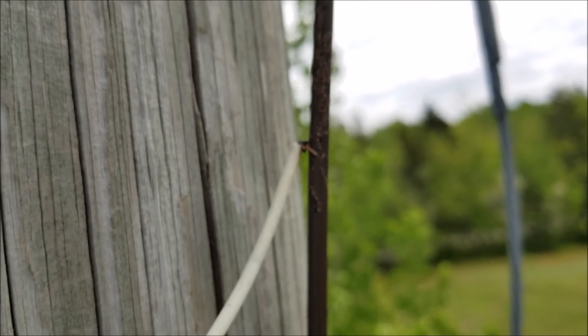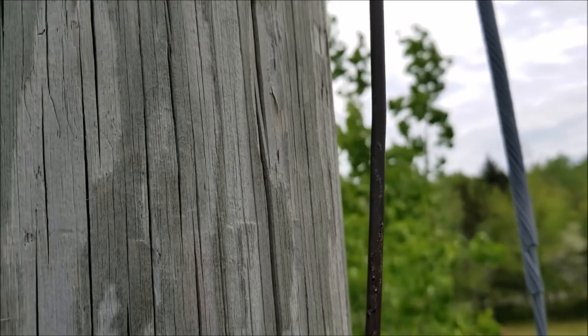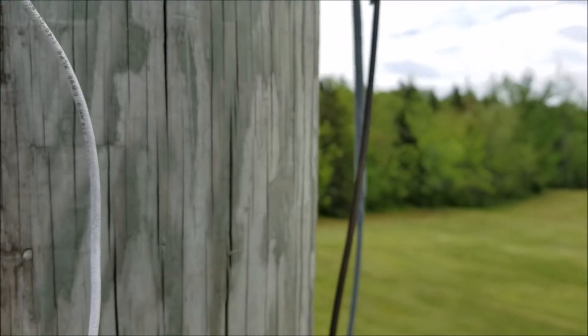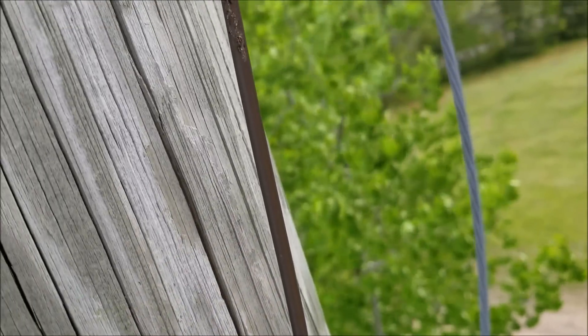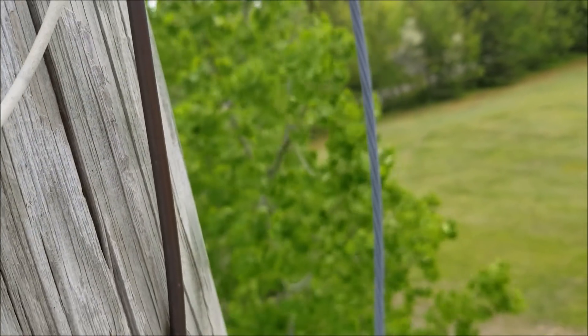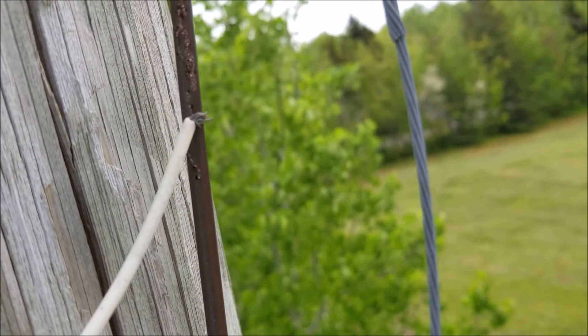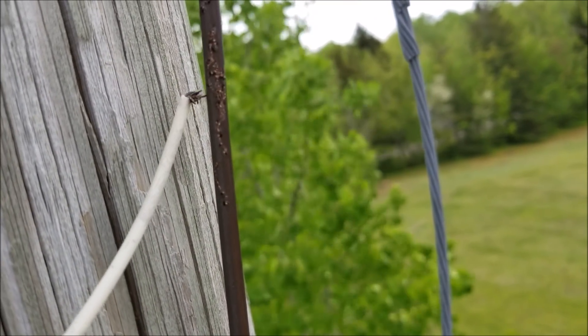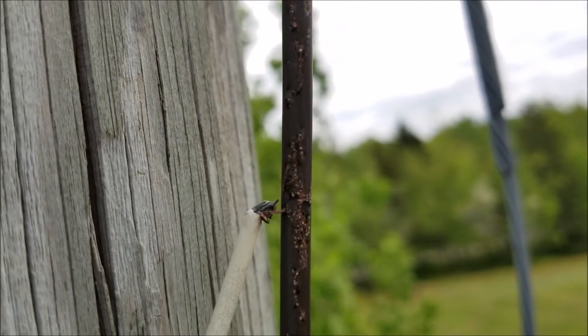I'm going to show you that clip one more time, keeping in mind the only return current is the result of one single light bulb trying to turn itself on. Now you can imagine an entire circuit, feeder, substation transformer — once you cut that ground wire you interrupt the electrical path's return back to source. Right here we have this neutral wire from a light bulb going to ground, and you can see it's actually drawn enough current that I'm able to melt the copper wire.